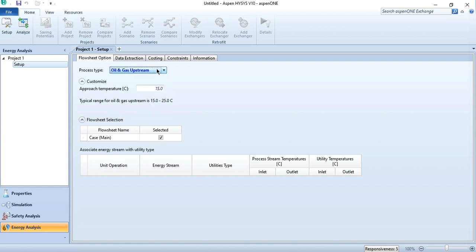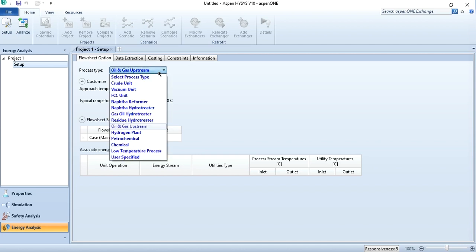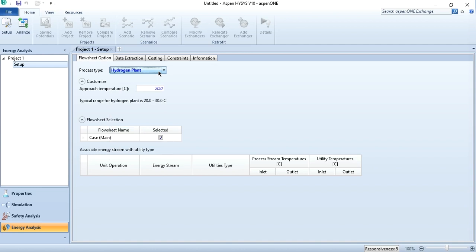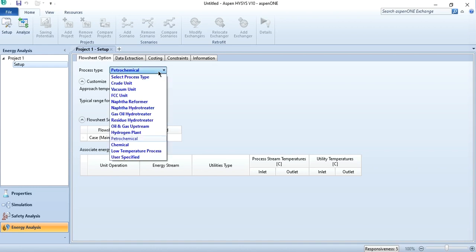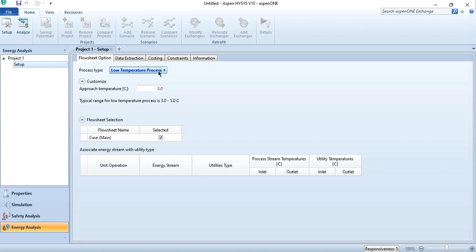For oil and gas upstream processes, the value is between 15 to 25 degrees centigrade. For hydrogen plants where hydrogen is produced, the range is 20 to 30 degrees centigrade. For petrochemical, the range is 10 to 20 degrees centigrade. For chemical systems, again, 10 to 20 degrees centigrade. And for low temperature processes where the system is operated below ambient — like for an air separation unit, which is a cryogenic separation process — this range can go to 3 to 5 degrees centigrade.